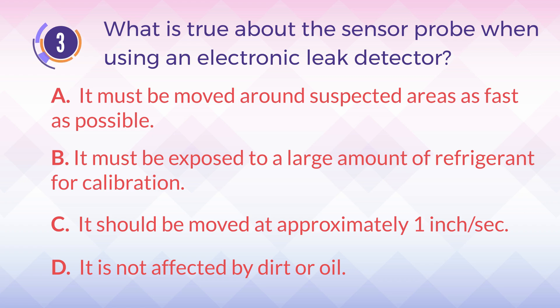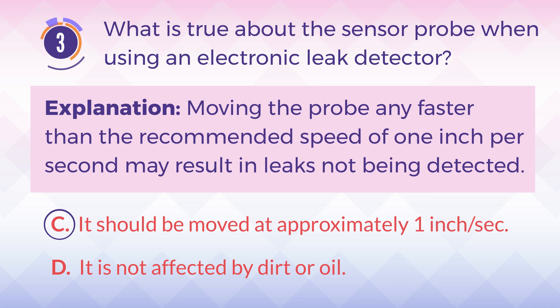The answer is C. It should be moved at approximately 1 inch per second. Explanation: Moving the probe any faster than the recommended speed of 1 inch per second may result in leaks not being detected.